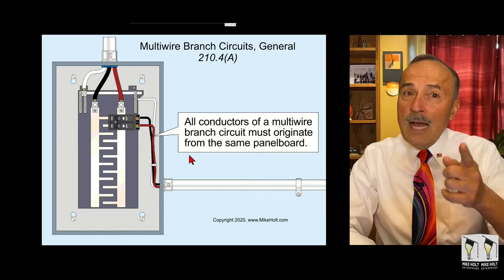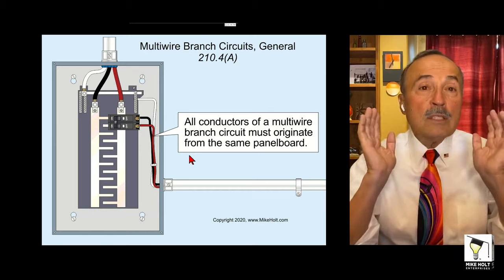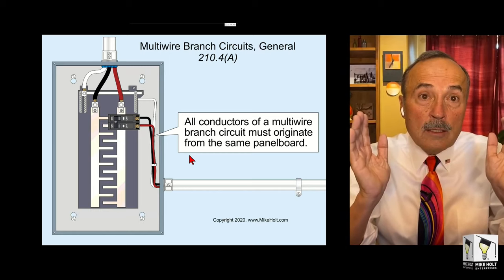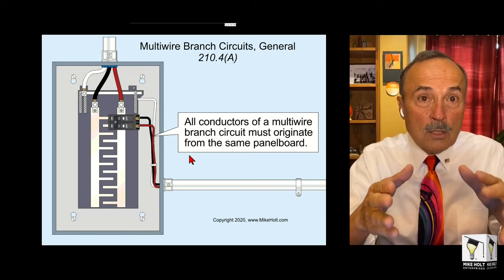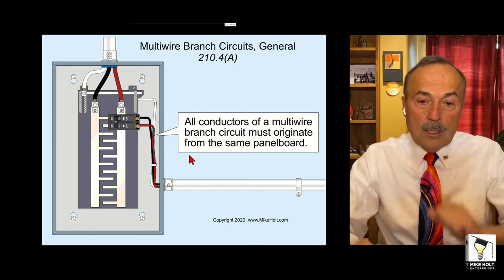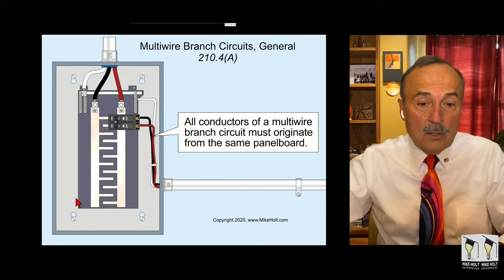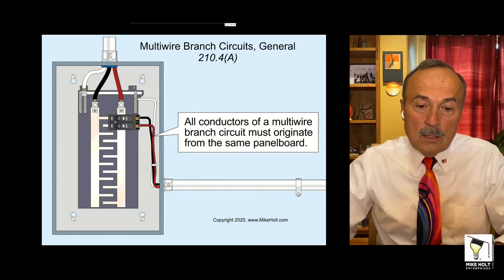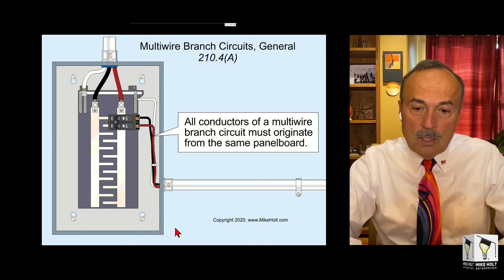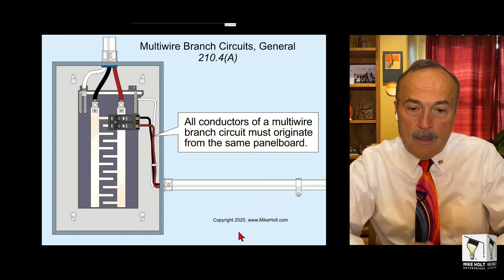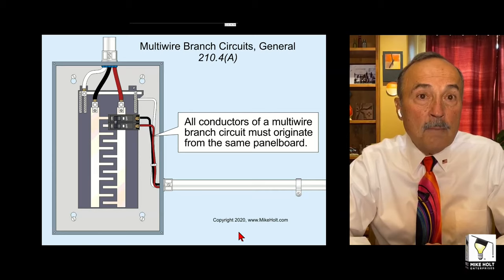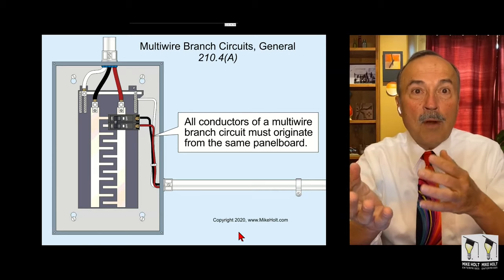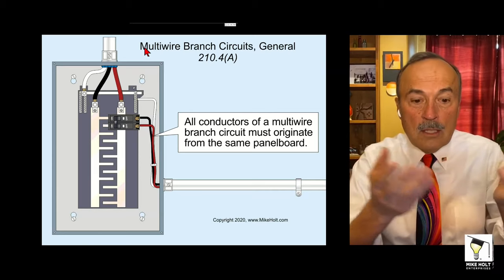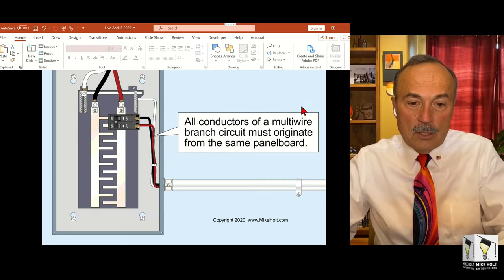But if current goes out on the hot, not returning on that neutral, well, then, of course, the AFCI is not even going to turn on. It's going to trip immediately, so you have to get them to work. So that's a multi-wire branch circuit. So what's the deal on multi-wire branch circuits? Here's what the code says. All conductors of a multi-wire branch circuit must originate from the same panelboard. Well, when the guy had the problem with different neutrals, different circuits, clearly that's a code violation.